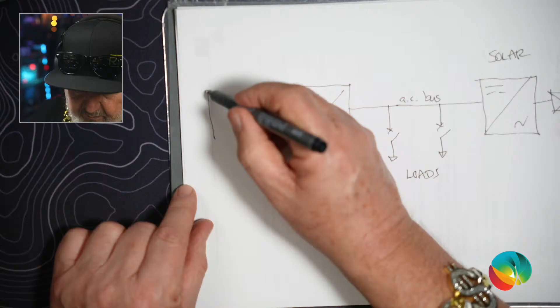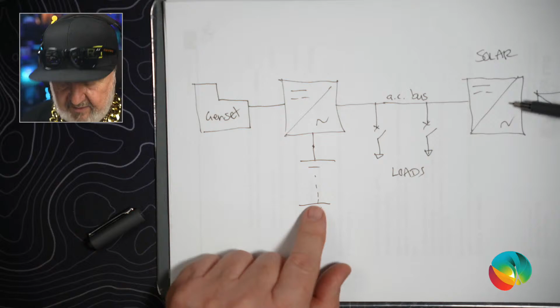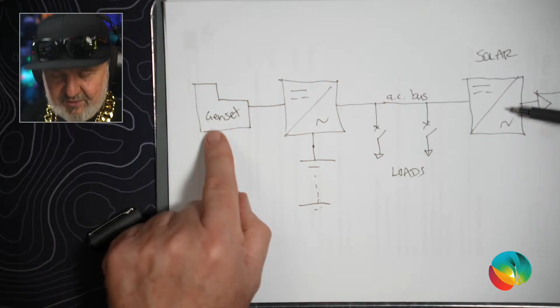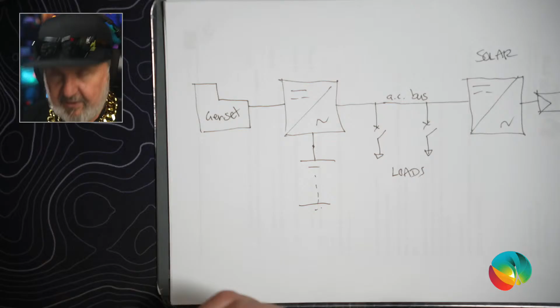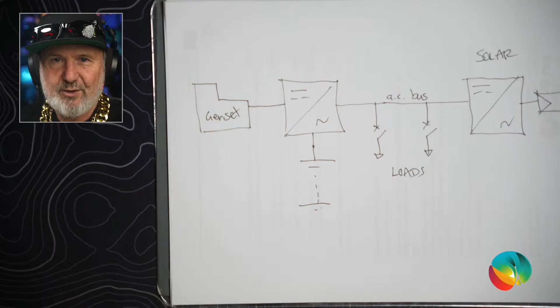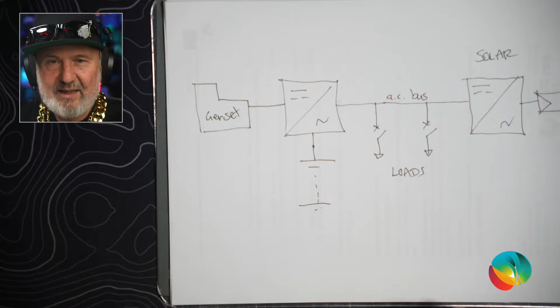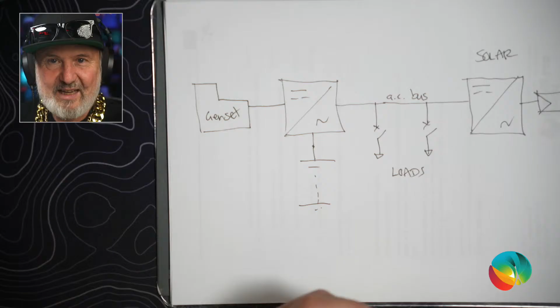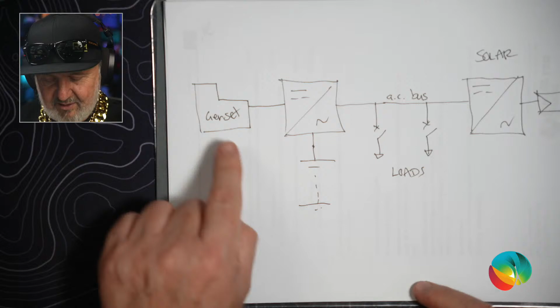But let's say we add a generator here, because if we're off-grid you really want reliability of supply, so we're putting in a gen set. Now you might think that's great, because if there's no solar and the batteries are empty at nighttime, I've still got a generator to keep everything alive. True. However, for those who have actually owned generators, there are probably about 10 reasons they don't work - most commonly low fuel, mechanical failure, or the starter battery is dead because it hasn't been used for so long. So this is an unreliable emergency source of power.